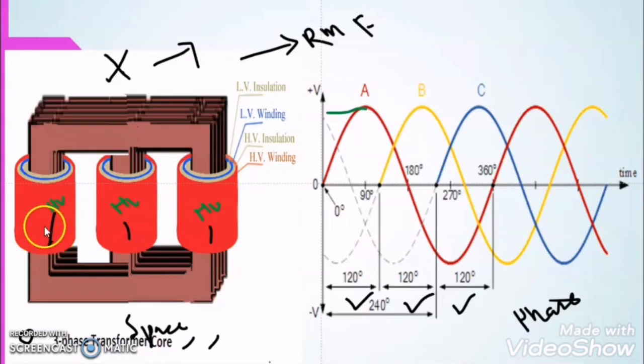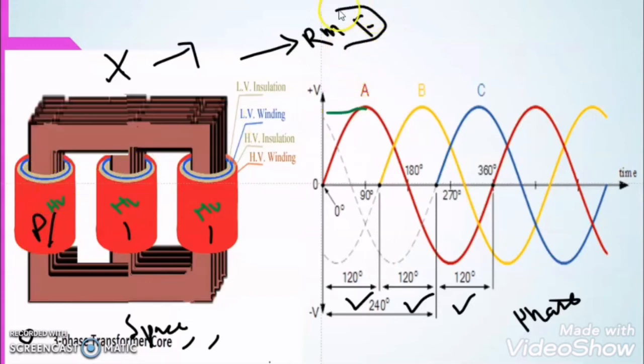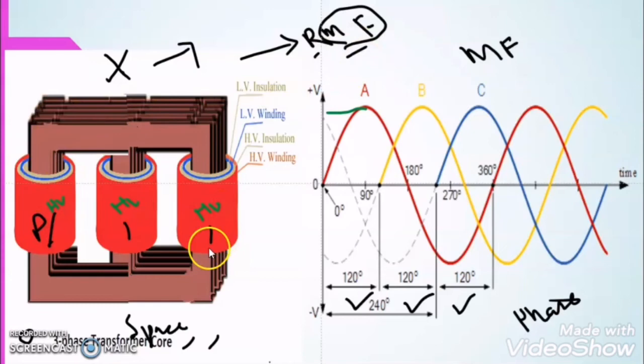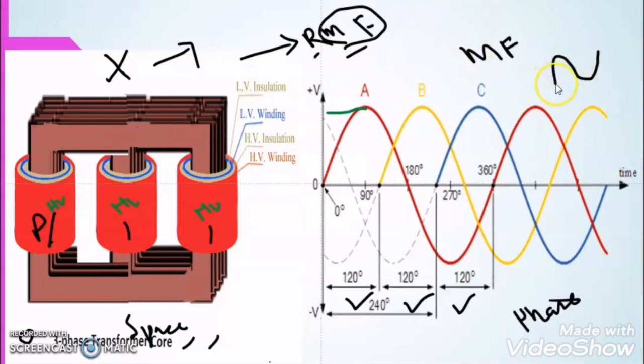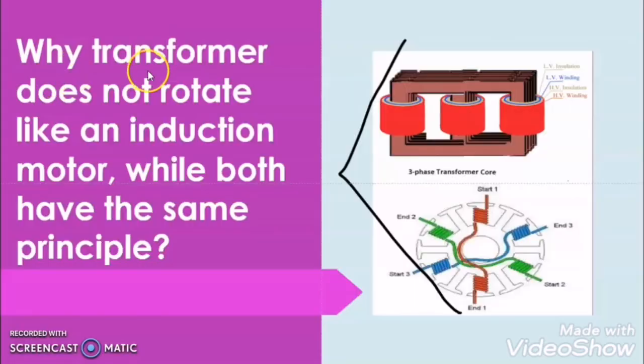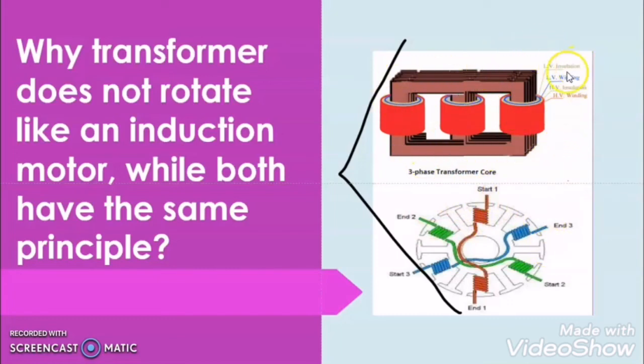In the transformer, the magnetic field developed due to the primary winding links with the secondary winding, but the nature of this magnetic flux is not rotating — it is pulsating. Due to the pulsating nature of the magnetic field in the three phase transformer, the secondary winding will not experience any force, as the field is pulsating and every time it is changing its direction. This is why the transformer does not rotate like an induction motor.